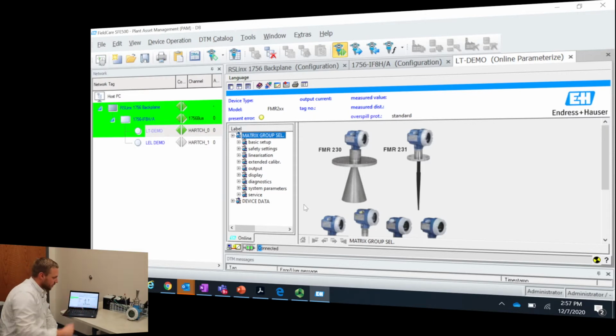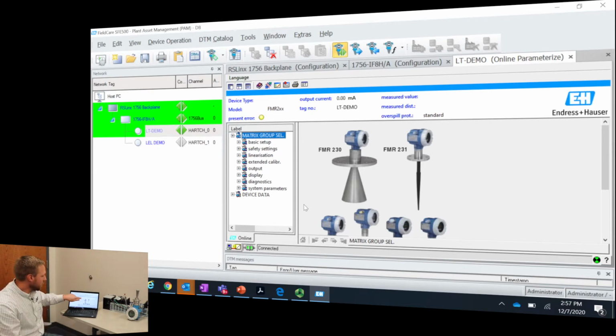We've got this little circle right here displaying status and that it's communicating. You'll see more and more of the information pull in here over time as it continues to pull it. Right now, this is the equivalent of a technician actually being on site, out in the field, connecting their HART communicator to the device, hooking up their clips directly to the leads coming out of it. However, obviously we're not doing that. We're able to do that very same function without being on the job site. All right, we are in.